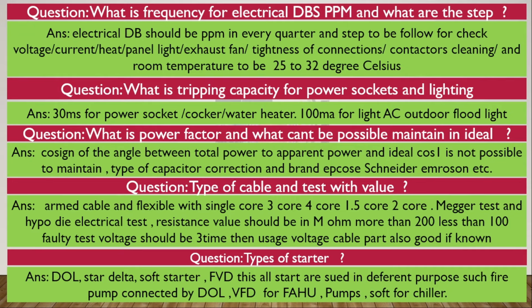Type of the starter, an important question. The types are DOL, direct online starter, star delta starter, soft starter, and VFD. These are all used for different purposes, such as fire pump connected by DOL, VFD for FAHU and pump, soft starter for chiller. The soft starter we mostly use for chillers, and the VFD mostly for AHU, FAHU and pumps, wherever we need automation.